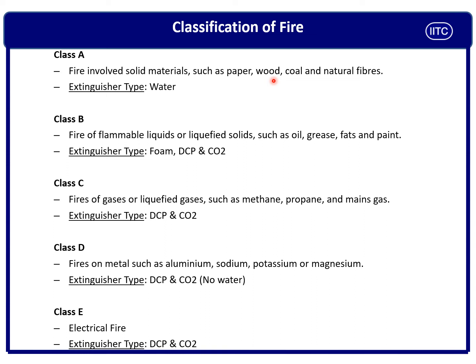If you are in the fire department, safety department, or are a plant or maintenance manager, you should know the classification of fire. There are five types — Class A, B, C, D, and E. Class A fire involves solid materials like paper, wood, coal, natural fiber, and plastic. For Class A fire, we use water to remove heat.